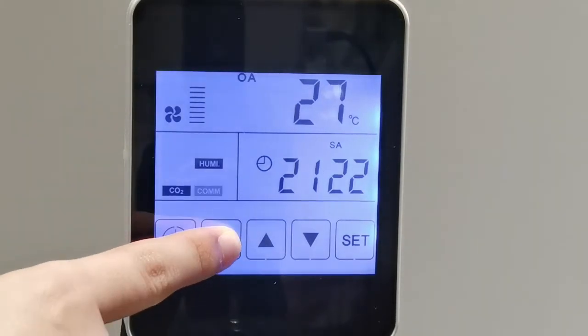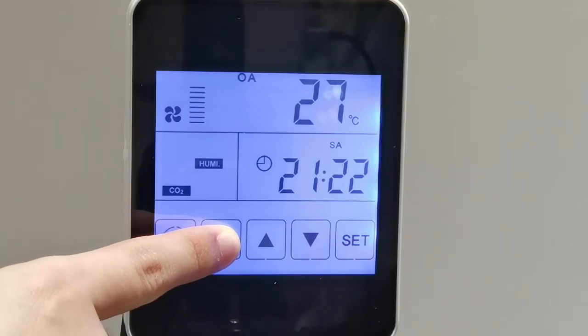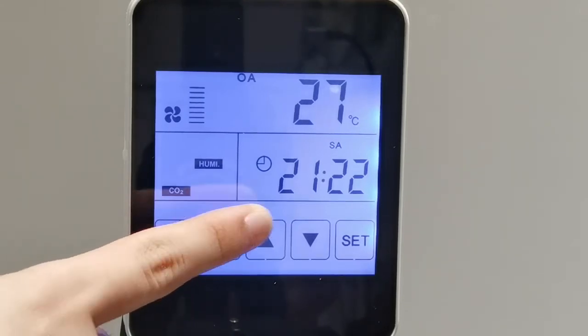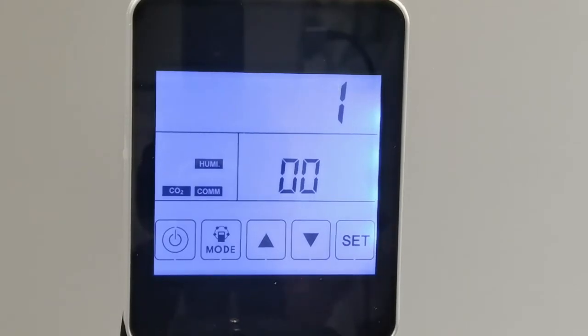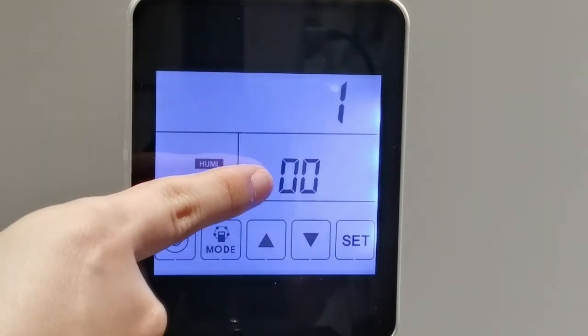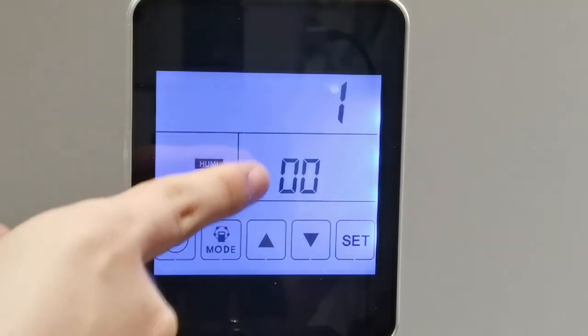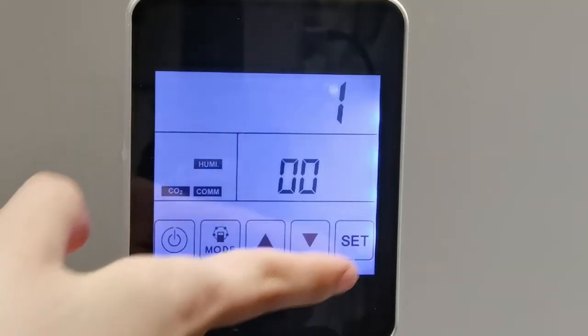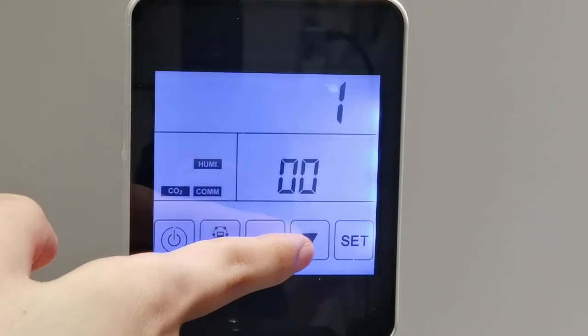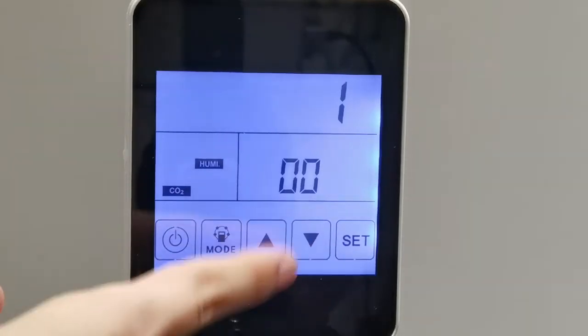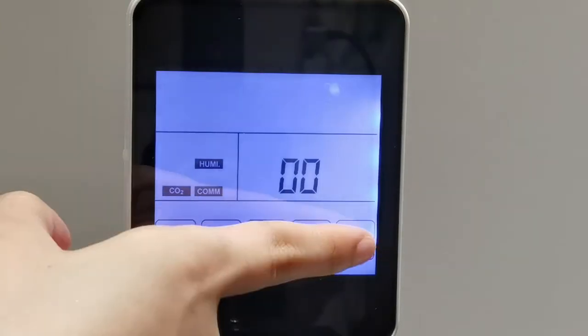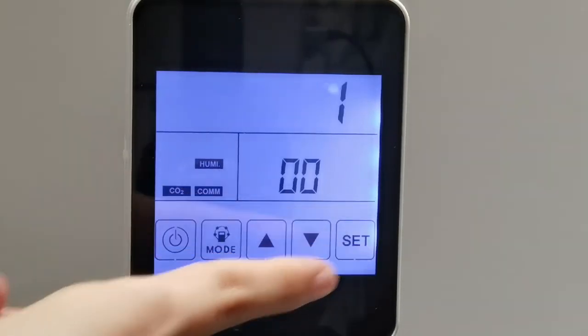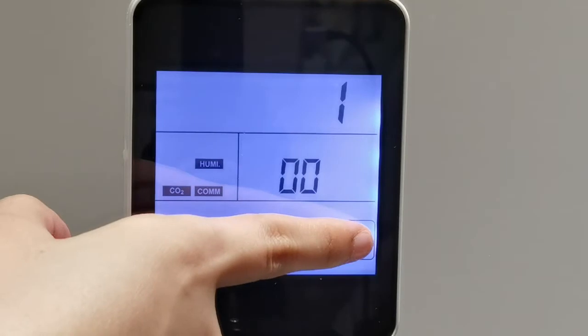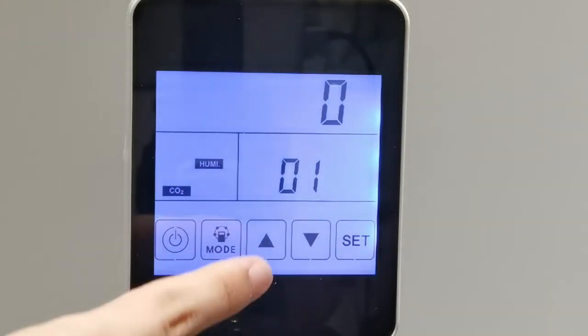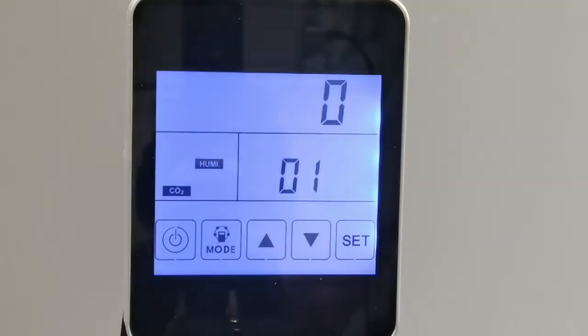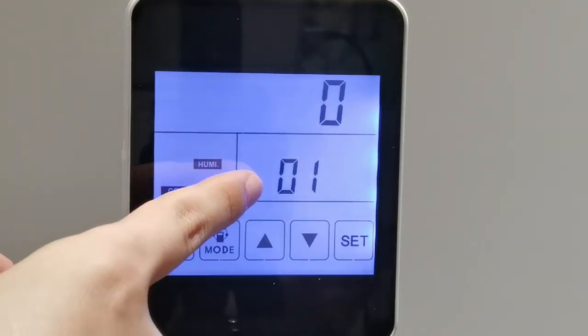Let's press the mode button for 6 seconds. Yes, now we enter parameter 00. It refers to power to auto restart. 0 is invalid, 1 is valid, and the default value is 1. Okay, and we press the set button to save the record. Okay, and press one more time to enter parameter 01.